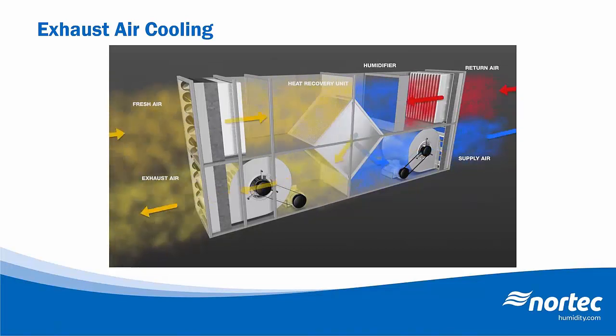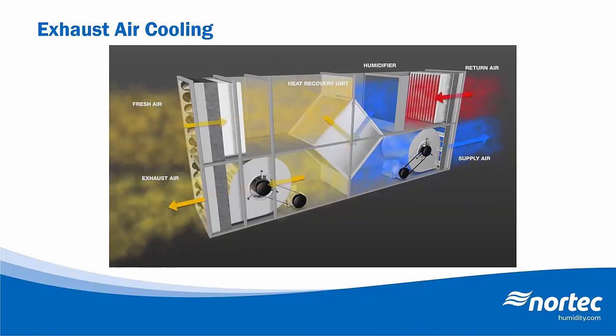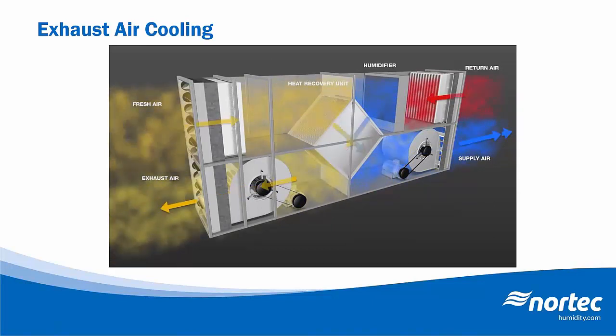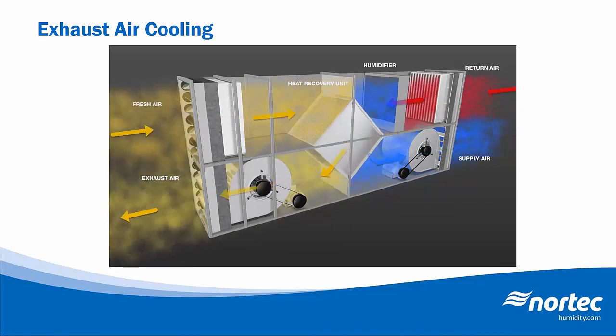Now, during summer months, this can reduce the temperature of the incoming air by several degrees as well as lower the need for DX cooling. During winter months, the warmer exhaust air can be used without the humidifier to preheat the incoming air, allowing reduced heating costs in the winter months. As there's no mixing of the air streams, there's no moisture added to the incoming air, so cooling here occurs irrespective of the incoming air's humidity level.